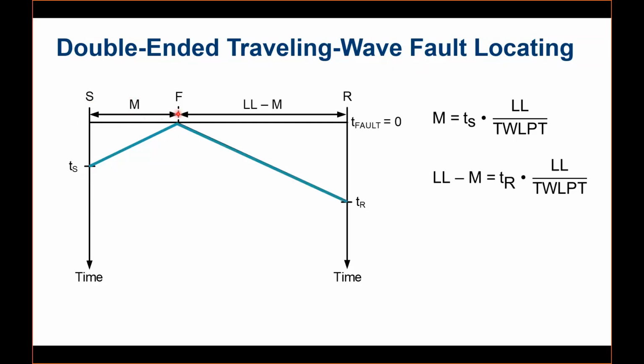With those relationships, if you have the formula for M, and similarly for the other line segment after the fault, you can just solve these two equations and find the value of M, provided you have these two times, TS and TR. TS is the time recorded by your local relay, and you should have the information from the remote end as well. You can just use those values, and the relay will give you a very precise fault location for point M.